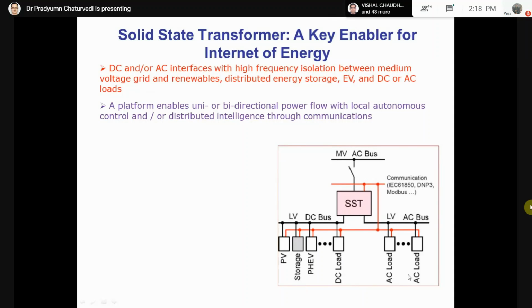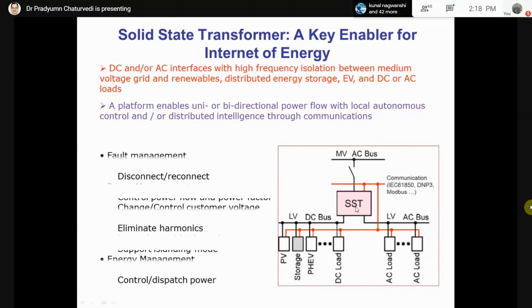So there is no dependency on the traditional grid and no dependency on a high frequency or low frequency traditional transformer, because this SST will take care of everything: isolation, voltage control, reactive power control, power quality improvement, protection system, everything, and power flow will be in both directions. This is the major advantage of this SST.